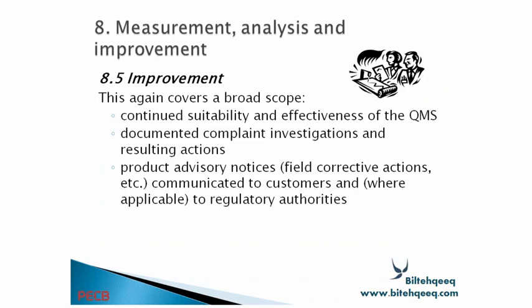8.5 is related to improvement. This again covers a broad scope: continued suitability and effectiveness of the quality management system, documented complaints, investigation and resulting action, product advisory notices, and field corrective action, communicated to the customer and, where applicable, to the regulatory authorities.